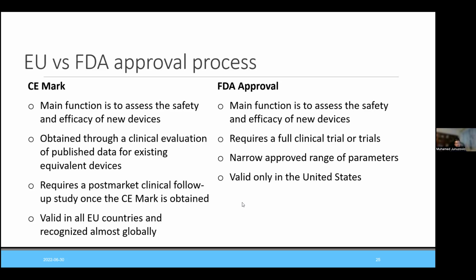Regarding the parallelizing of processes, for example, if you design and develop a Faraday cup, you have a device, you do a lot of testing. And at the end, to use this as a component of a medical device, you need to have documented test reports, and not only test reports but also the design of the Faraday cup. Maybe the group which will do design, manufacturing, and testing will not have time to do everything in a proper way. So there will be some sketches, but at the end, we need to have a proper design document. So this is an example where additional effort can be required if you do CE marking on top of development. I hope it's a little bit more clear now.